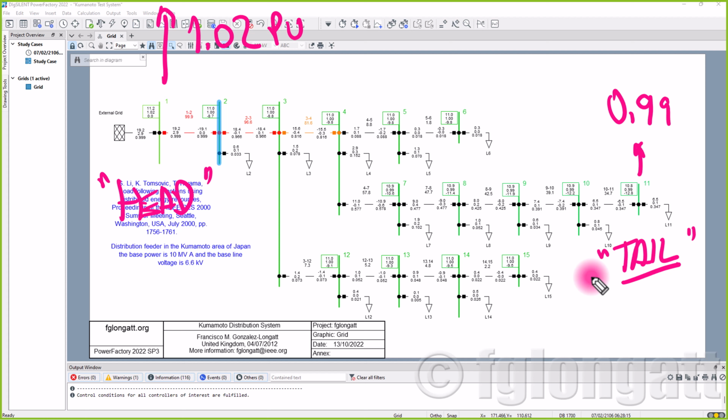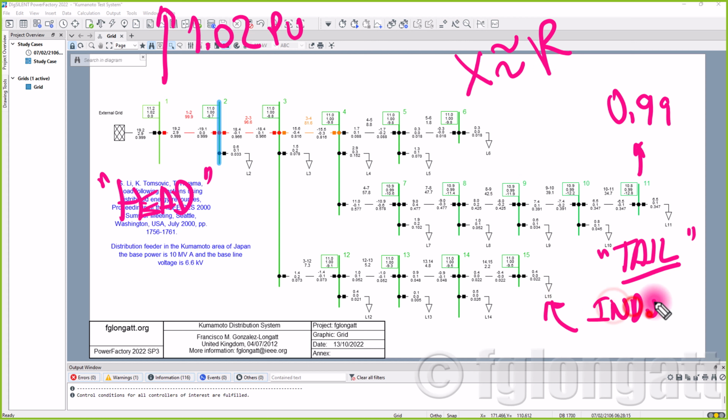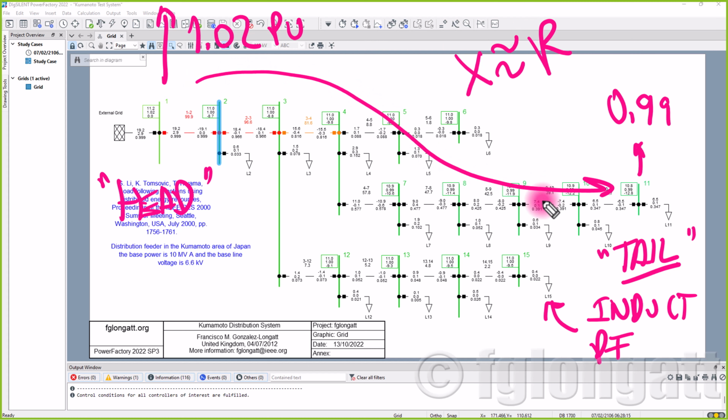I say the classical situation, why? Because in distribution systems, there are different things that can happen. In a very old distribution system like this, year 2000, classical distribution systems have a reactance that is almost similar to the resistance. For that reason, if we have loads with an inductive power factor, or lagging currents, with a reactance that is similar to the resistance in the overhead lines, that will create this situation.